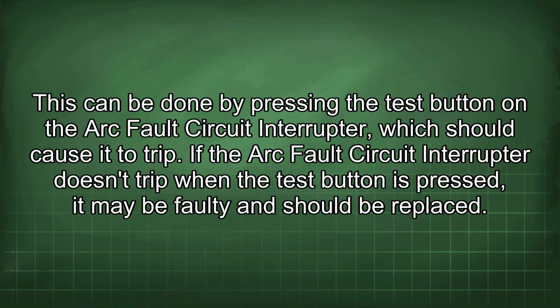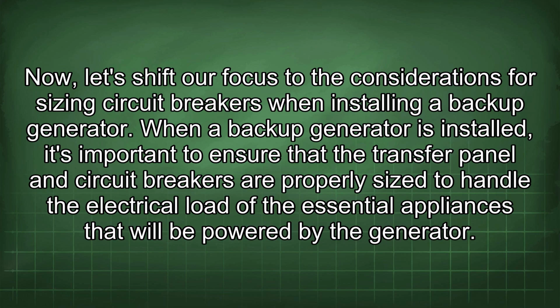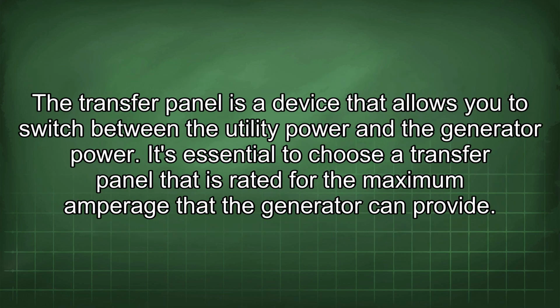Now, let's shift our focus to the considerations for sizing circuit breakers when installing a backup generator. When a backup generator is installed, it's important to ensure that the transfer panel and circuit breakers are properly sized to handle the electrical load of the essential appliances that will be powered by the generator. A transfer panel is a device that allows you to switch between the utility power and the generator power. It's essential to choose a transfer panel that is rated for the maximum amperage that the generator can provide.